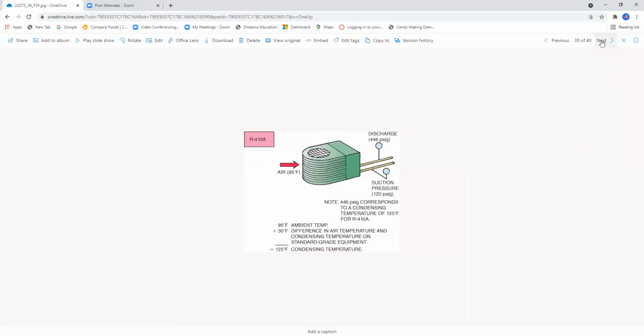Okay, this is an R410A split system. Notice that we have a 95 degree ambient, and the suction pressure with 410A is going to be 120 PSIG, with 446 on the high side. The 446 corresponds to a condensing temperature of 125 degrees for R410A. 95 degrees is the ambient temperature in this design picture. That's a 30-degree difference between the air temperature and the condensing temperature on standard grade equipment. So we're talking about a 13 or 14 SEER unit, with a 125-degree condensing temperature.